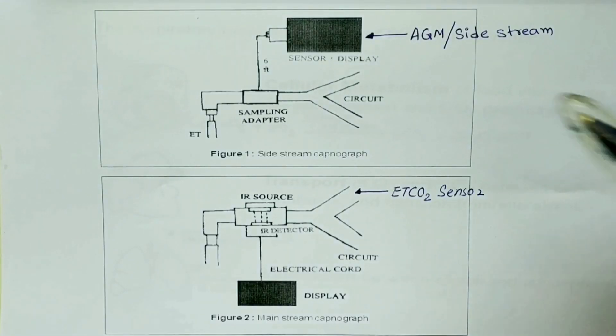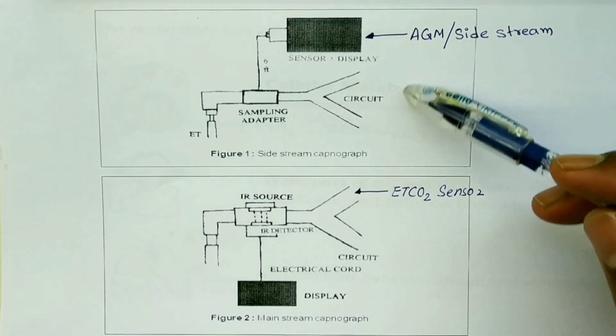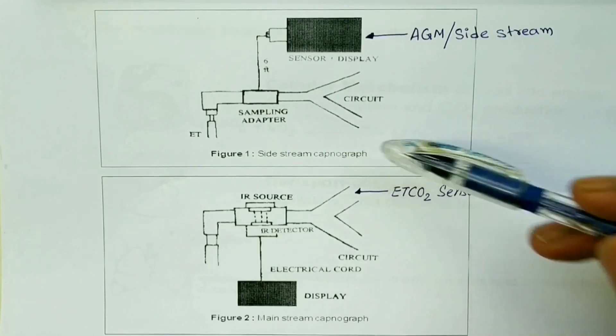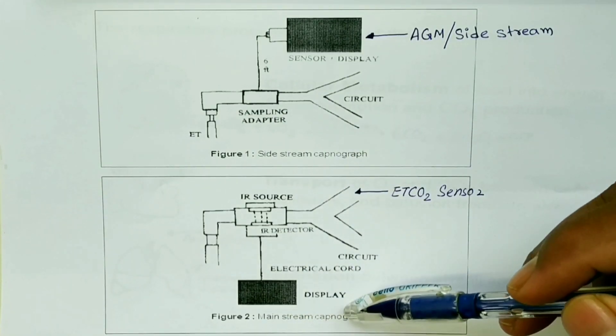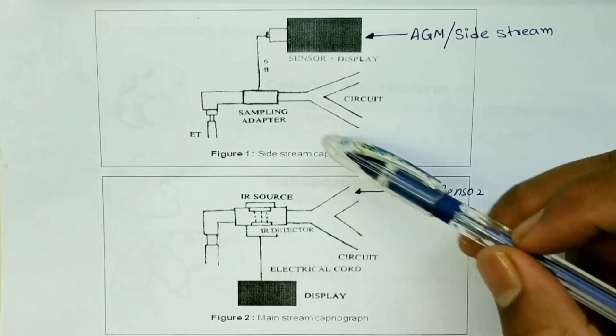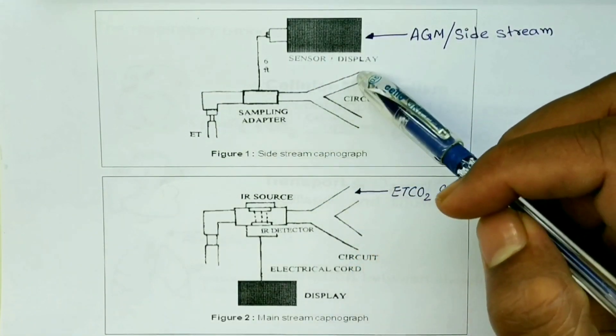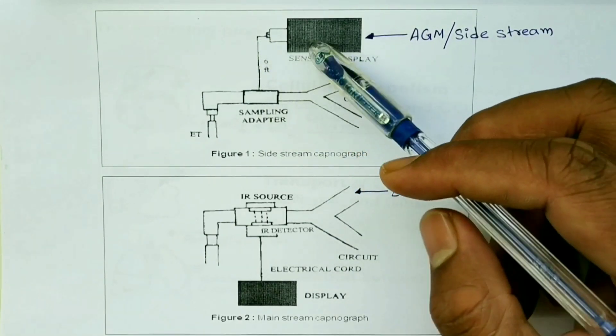The ET CO2 can be taken by two ways. First is the side stream capnography, and then it is the mainstream capnography. In side stream capnography, there is a sampling line attached to the ET tube and this goes to the ventilation circuit. From this, it goes to the AGM or the side stream detector, and there is a sensor and display which calculates the ET CO2.